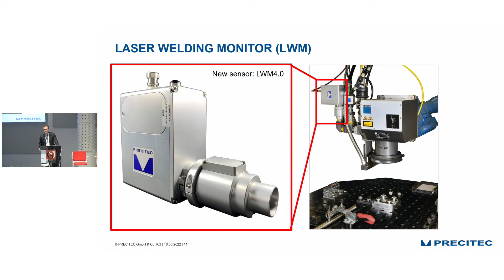Now, seeing this sensor in action can be seen in this video. At first you can see the photodiode which is sensitive in the visible range of light, and second the photodiode which is sensitive in the near infrared. If the current sensor signal, highlighted here in blue, is between the limits, the envelopes, then we say it's a good weld. If it is outside the limits, as shown here, then we give information to the PLC in real time saying, pay attention, there was something wrong. So, a system and a sensor based on comparison.